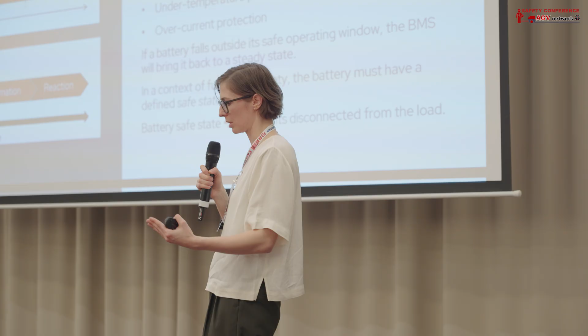The reaction time depends on the abuse, of course. But we have the most important safety functions implemented in the BMS: overvoltage, undervoltage, overtemperature, undertemperature, and overcurrent protection. With our Micropower batteries, we can actually achieve Performance Level D for all five of those functions, so we exceed the requirements of the legal standard.